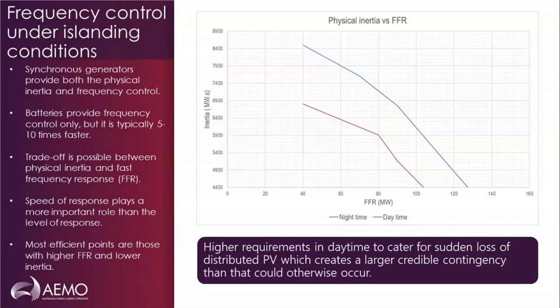And the last point, which again I'm only touching here, that might warrant a separate discussion at a different time, is the question that may come up: why do we have two sets of curves? As highlighted in the legend, you can see that we have a daytime requirement and a nighttime requirement, and the daytime requirement is higher. And this is simply because of the factor that I was mentioning earlier, that in some periods we could have a significant penetration of distributed PV, which doesn't come with the same level of control and flexibility that a large scale PV or wind farm would come with.